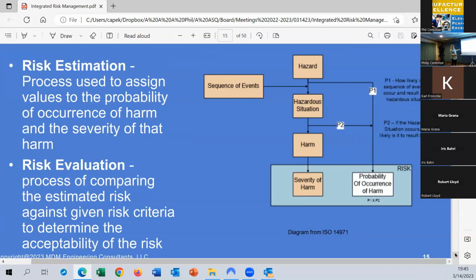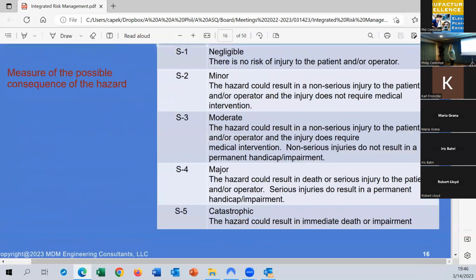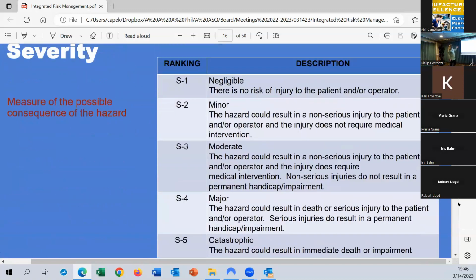Once we estimate risk and evaluate it, we want to compare the estimated risk against given criteria to determine if the risk is acceptable. So we estimate risk and then we say, okay, can I live with this risk or do I need to reduce it? So this is an example severity table. Again, a severity of 1 would be something negligible. A severity of 5 would be something that could result in immediate death or impairment. That would be something catastrophic, and everything in between.